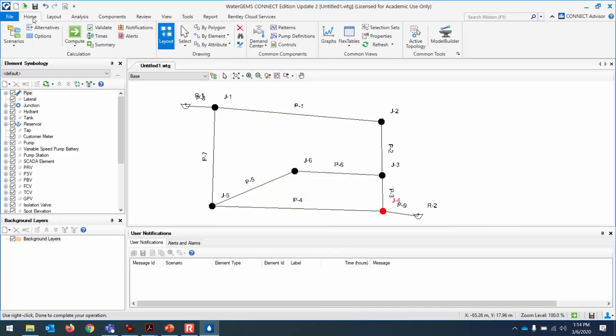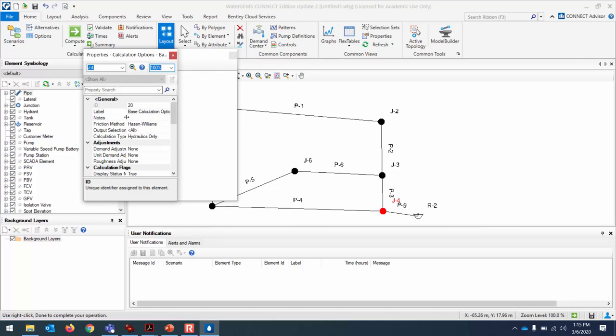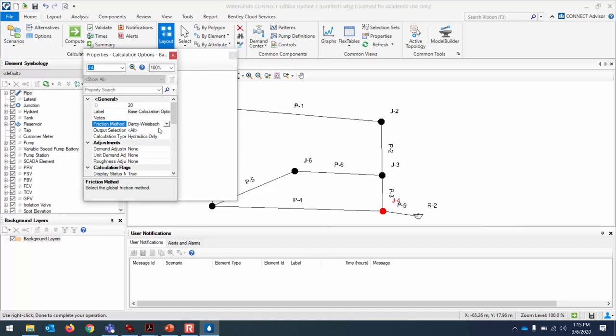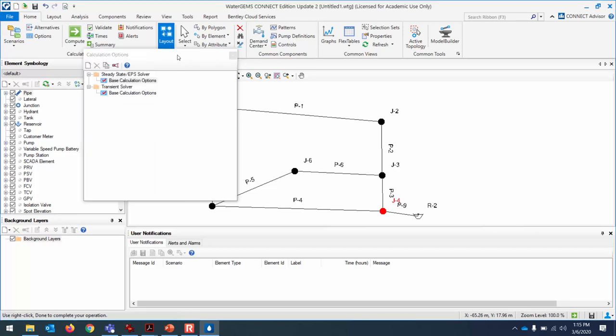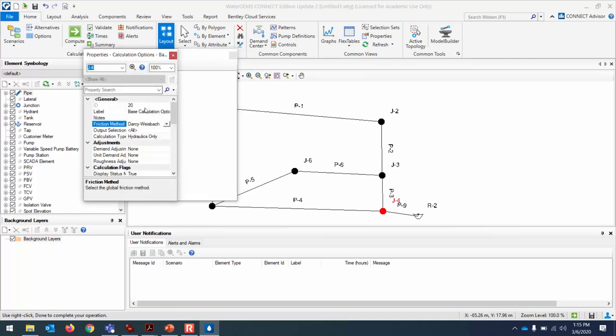Make sure the software uses the Darcy-Weisbach equation for calculations, because by default it uses Hazen-Williams, which is less accurate. Go to Home > Options > Base Calculation Options (under the steady state menu), double-click, and toggle the friction method from Hazen-Williams to Darcy-Weisbach. Earlier this morning the wrong method was set and the flow rates and pressures weren't matching expectations.